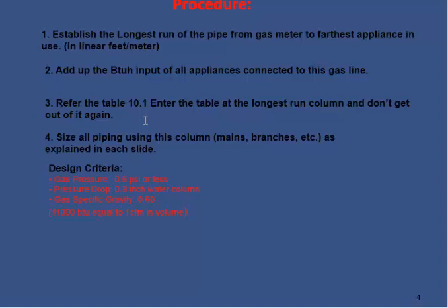The design criteria taken for this presentation is: gas pressure 0.5 psi or less—generally domestic gases are supplied at this pressure—pressure drop of 0.3 inches water column, and gas specific gravity of 0.6. Also, 1,000 BTU equals 1 CFM of natural gas.